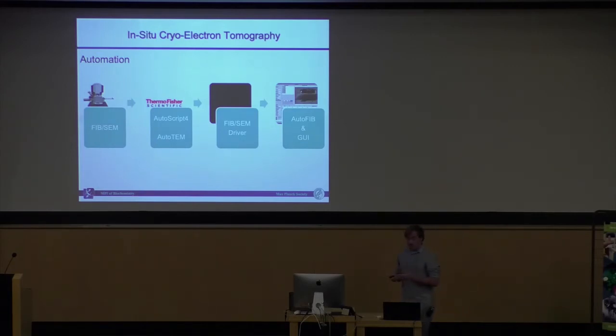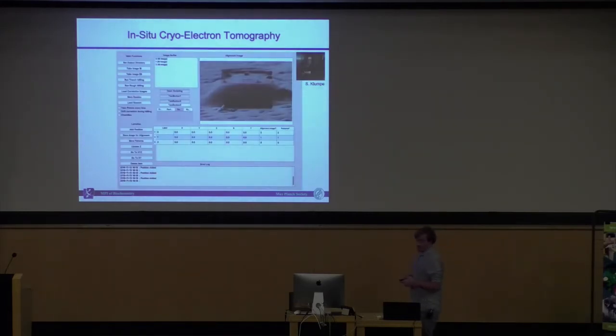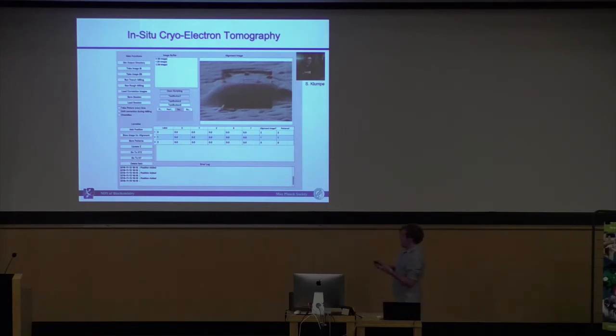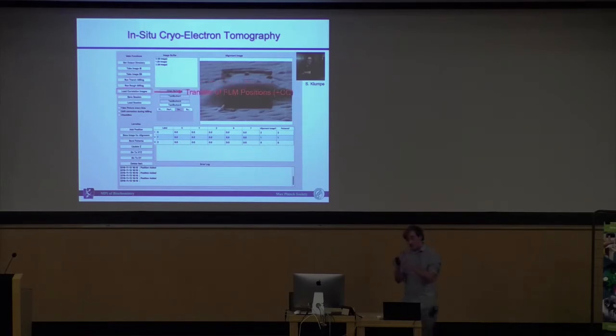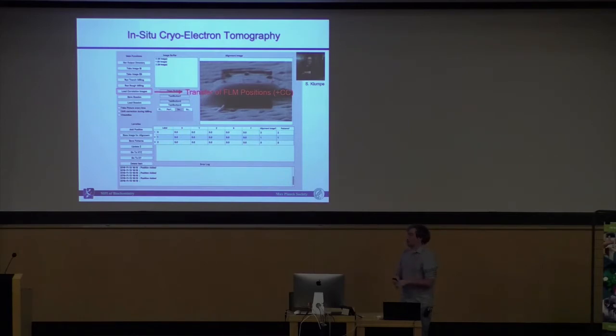This automation software has all the things you want — trench milling and everything else. What's very important for me is that we can load correlated images and use cross-correlation. When you do your alignment with fiducial markers, there's some drift on the scope — your image will be slightly different, making it hard to find exactly where to cut your lamella. This will do that for you: cross-correlate with the previous image, find exactly the same spot, put your pattern where it's supposed to be, and start your milling process.